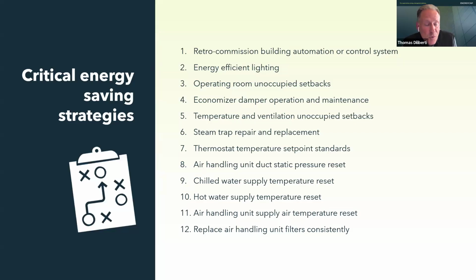That's true for chill water, hot water, and also for number 11, air handling units and supply temperature. Occupants in a building always need fresh air, but the air being delivered to the spaces can change to keep people comfortable. That's the idea behind number 11 - resetting the air temperature to accommodate people in the building while minimizing energy use.